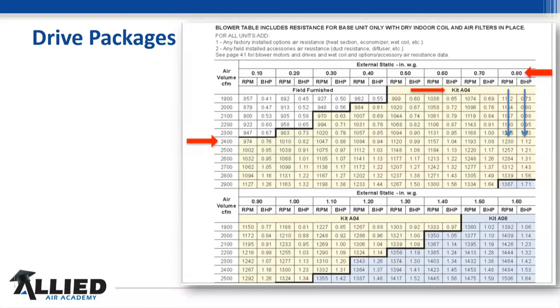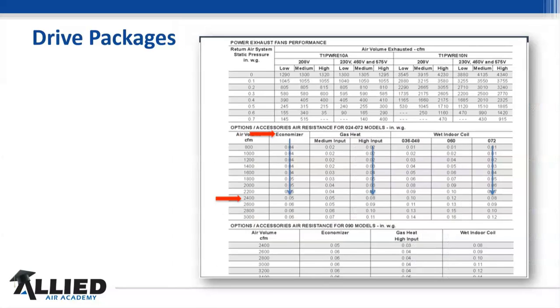But we always design these units to a dry indoor coil. And that's an industry standard. That's not just an Allied thing. That's an industry standard, because if you go and try to pick out a specific humidity and all this and then test to that, the test standards would be difficult to actually get in there and do.